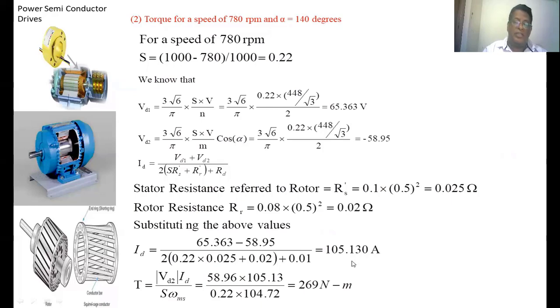The torque developed in the induction motor with Scherbius drive = Vd2·Id/(S·ωs). We know Vd2 = 58.96V and Id = 105.13A. Substituting: T = (58.96 × 105.13)/(0.22 × 104.72) = 269 N-m. This is the torque developed in the induction motor at 780 rpm and firing angle 140°.